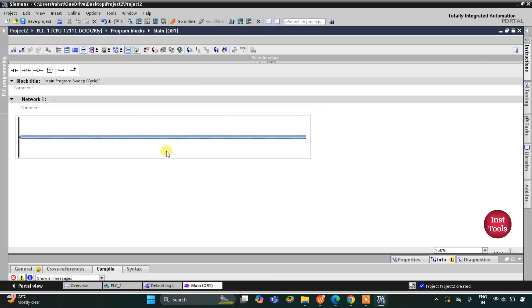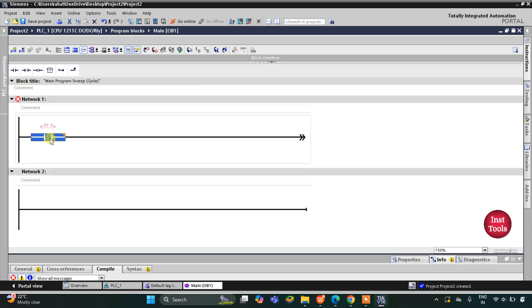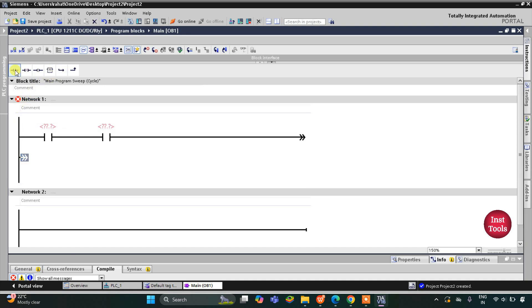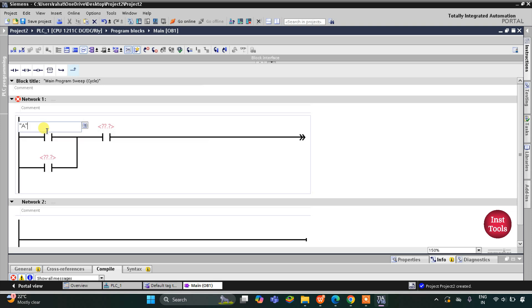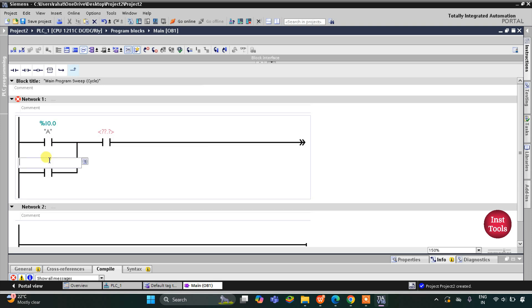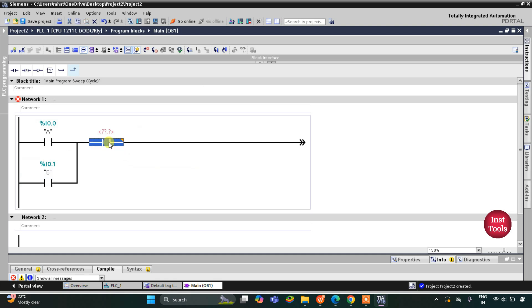In Program Blocks, Main OB1, we will draw the ladder diagram. For A, I will use a normally open contact. For B, I will open a branch and add a normally open contact connected in parallel with A, then close the branch. Then I'll add a normally closed contact for C, since there is a NOT logic gate with C.